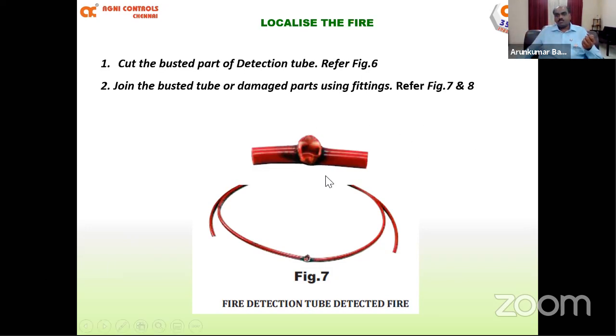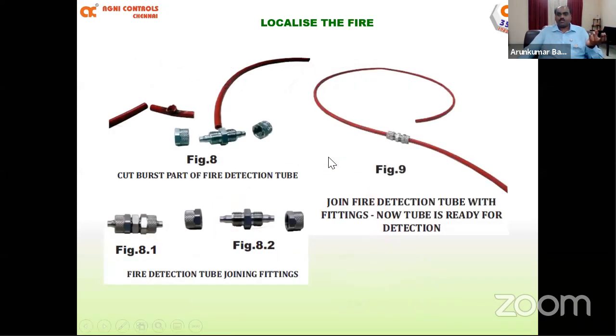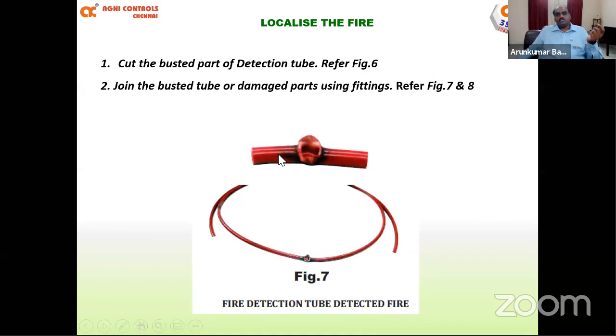If you see here, this is exactly how a detection tube looks when it bursts due to a contact with a hotspot or a fire. If you take an example of this kind of tubing, in this entire tube only this particular spot is in a burst mode. All the other tube is in very good condition. So we don't need to change the entire tube length.